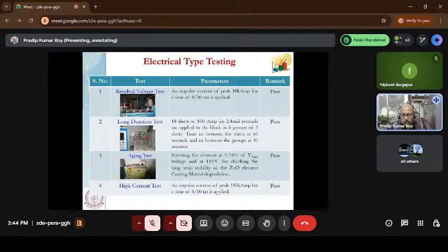And the high current testing tells how useful the coating is, and how successful the coating is after maturing the glass coating. For that we need a 4 by 10 microsecond impulse for 100 kiloampere current, and that tells the strength of the glass coating you put around the block. Then this ageing test is required. The ageing test normally tells whether any leakage is happening through the blocks or not. As I said, it's an outdoor application, so we also check whether any humidity effect is affecting their performance.